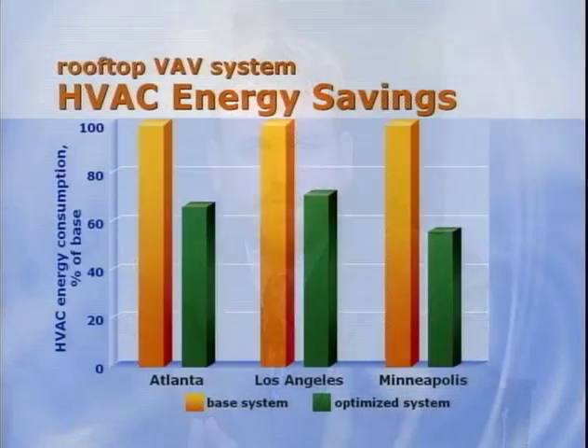The results show that there is potential to improve the energy efficiency of rooftop VAV systems. The orange column to the left for each city is the base case, and the green column to the right is the optimized system. The y-axis is overall HVAC energy consumption, shown as a percentage of the base case. The optimized rooftop VAV system reduced the HVAC energy by 35% for the building in Atlanta, by 30% in Los Angeles, and by 45% in Minneapolis.